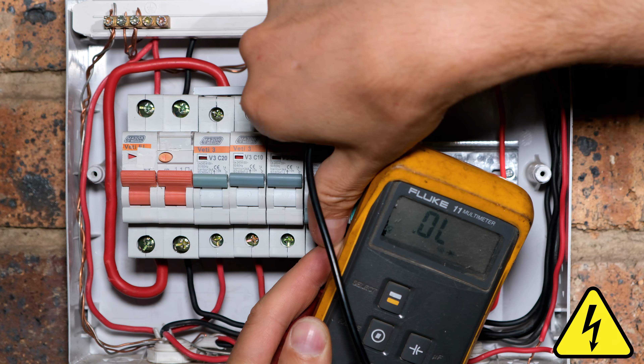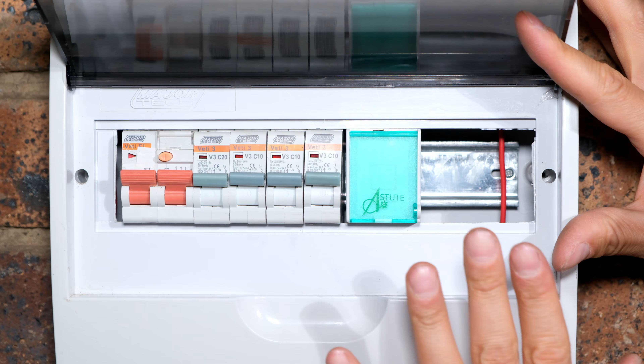So I'm going to lift the circuit breaker up again, and now I'm going to quickly measure at the timer, and you should see the 230 odd volts. And there we go. So the timer is now energized and it's ready to be configured. Now you can also check the status of your timer by looking at the front of the unit, and you'll see there is a little red LED telling me that the unit is energized. At this point you should return the cover, and you should not work while the cover is open. But for this video I am going to just work with the cover open, just for demonstration purposes.